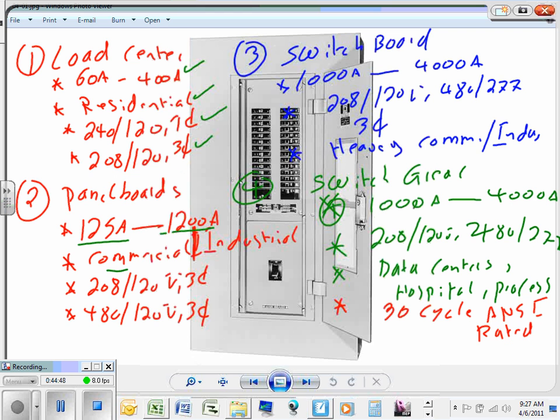Where would you use them, guys? Commercial and industrial. What voltages? The most common voltages for these are 208/120, 480/277, and this should be three-phase. That's mostly the most common. A lot of commercial buildings, guys, have panel boards, panel boards that can go all the way to 1200 amps. 1200 amps at 480 is a lot of power. So don't think it's nothing. 1200 amp at 480/277 is a lot of power.